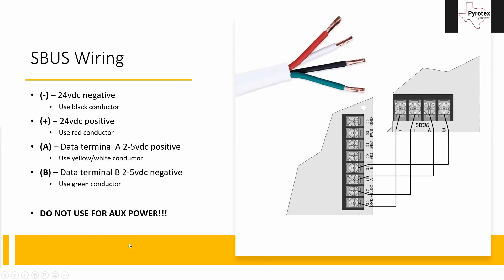One important note: do not use the positive and negative on the SBUS terminals for auxiliary power. Don't use it for door holders, your sprinkler bell, or to power a cellular dialer running off 24 volts. I know the Silent Knight panels don't have a dedicated auxiliary power terminal, so it can be tempting to grab power off the SBUS terminals — but it's not made for that and can cause communication problems. It can pull that voltage down and cause problems with your power supplies in the field. There are other ways to accomplish those tasks, so pick up the phone and figure out the right solution.